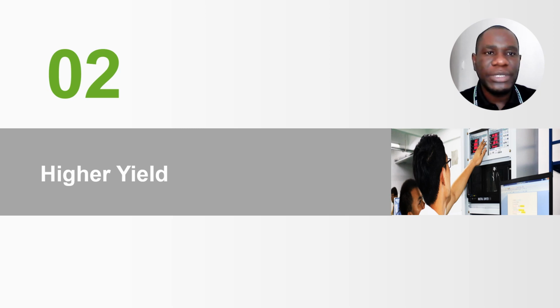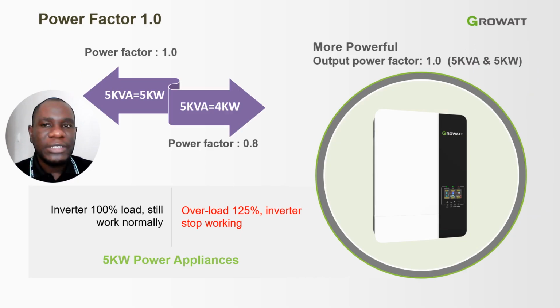Moving on to the yield. These inverters generally have got a higher yield as compared to other inverters. As you can look on the power factor, it has got a power factor of 1, meaning that a 5 kVA inverter has an equivalent usable power of up to 5 kilowatt because of the power factor of 1. If you compare with other off-grid inverters on the market, you'll find that they've got a power factor of around 0.8, meaning that if you've got a 5 kVA inverter, you won't get 5 kilowatt from that inverter.